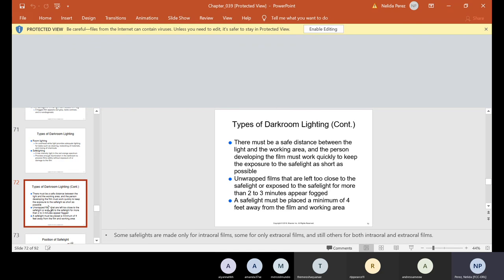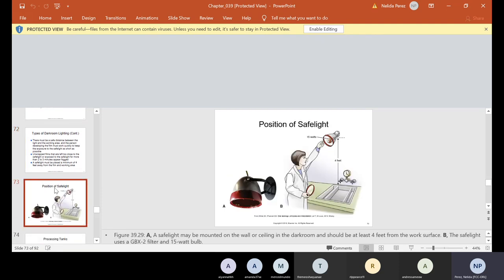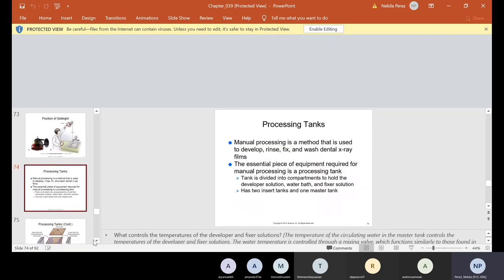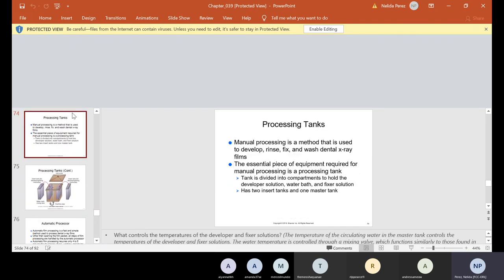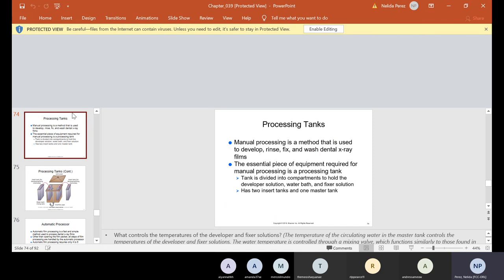Unwrapped films exposed to the safe light for more than two to three minutes appear fogged, and a safe light must be placed a minimum of four feet away from the film and the working area. Moving on to the automatic processor — it's a fast and simple method. Other than opening the film packet, all steps of film processing are handled by the automatic processor. The errors usually come from the operator: not putting it right in the rack, exposing it to light, forgetting to turn on start, or forgetting to close the lid.